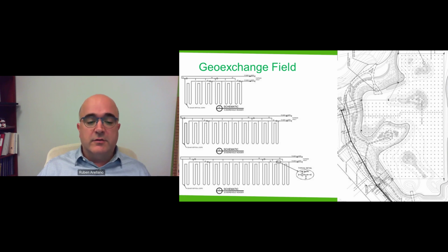So you have a series of header circuits, shown on the left, piped in a reverse return arrangement designed to allow for efficient, low head loss pumping, while equalizing flow through all the boreholes.